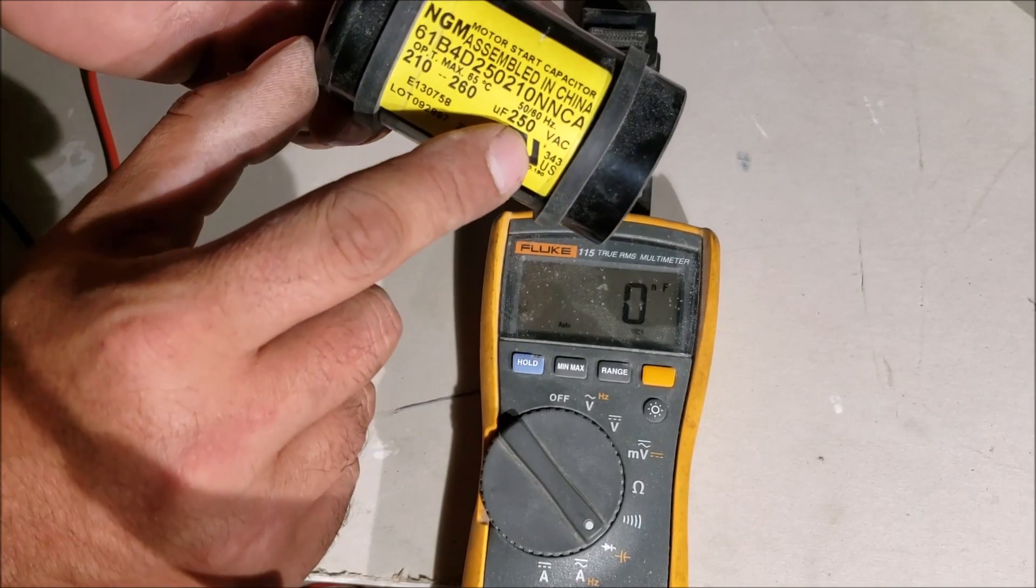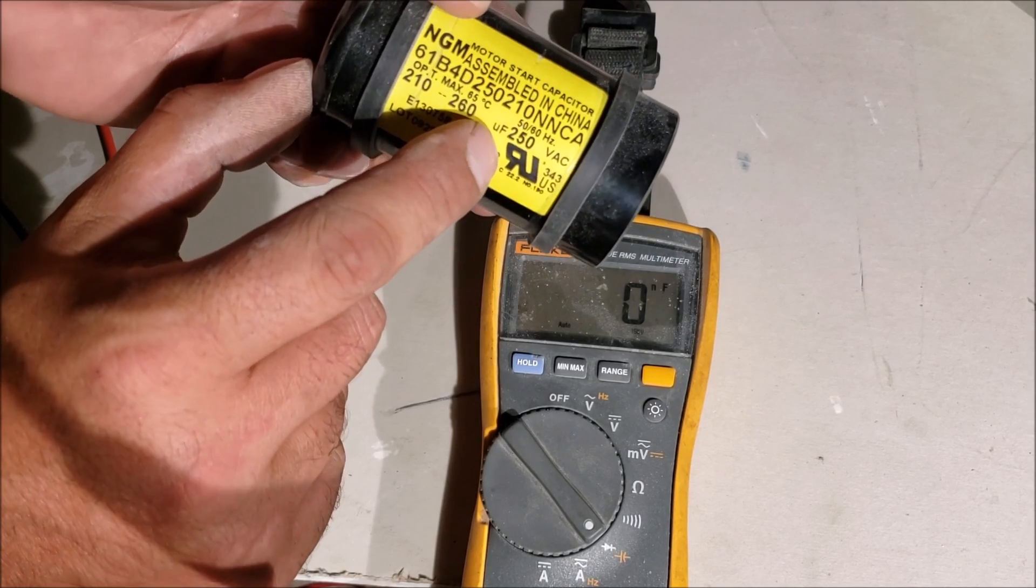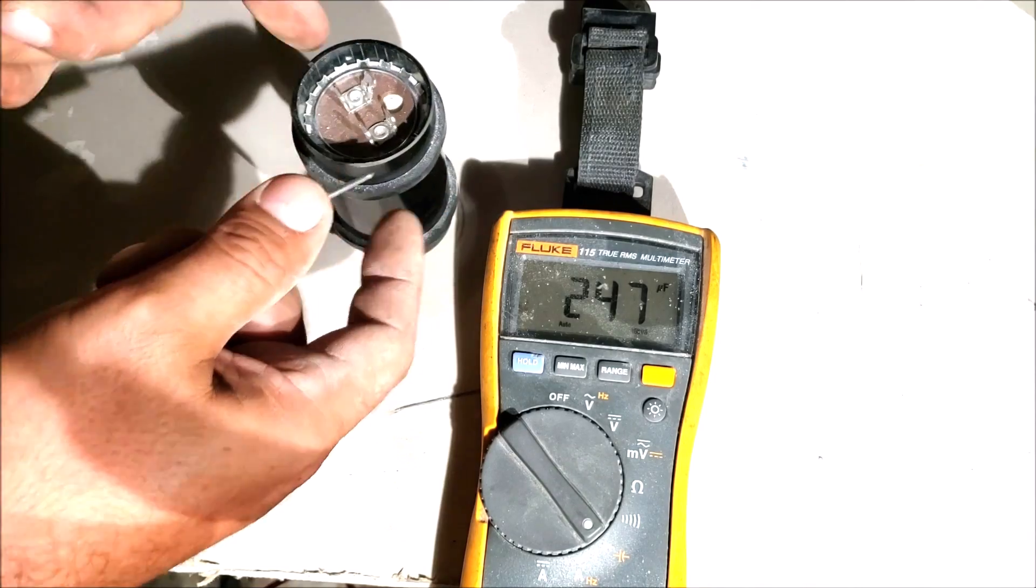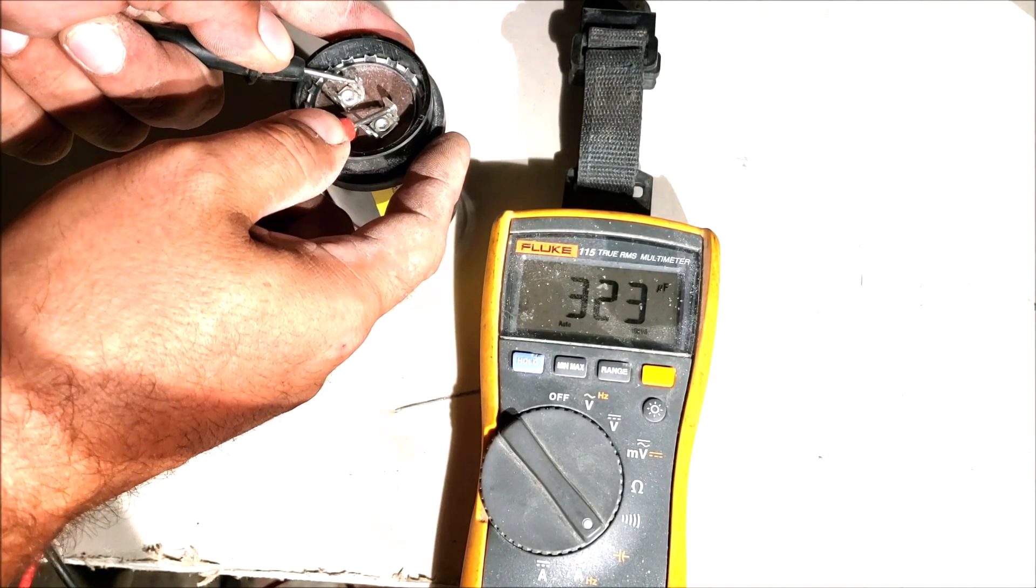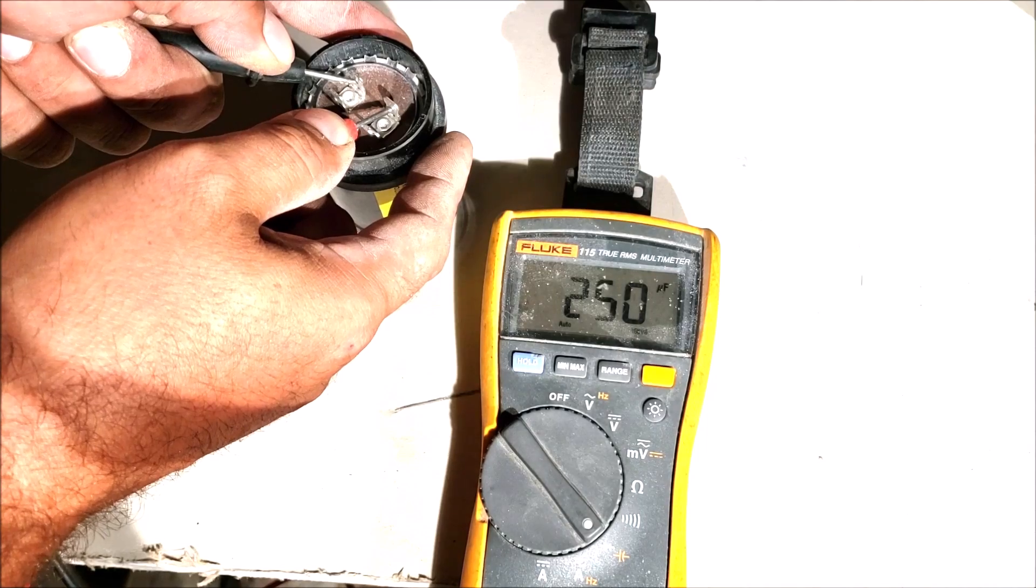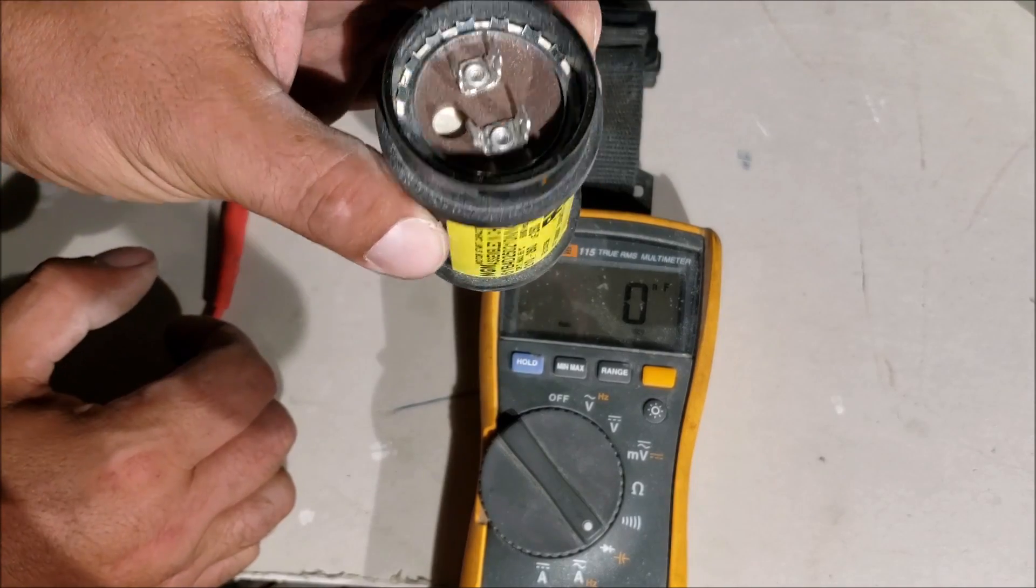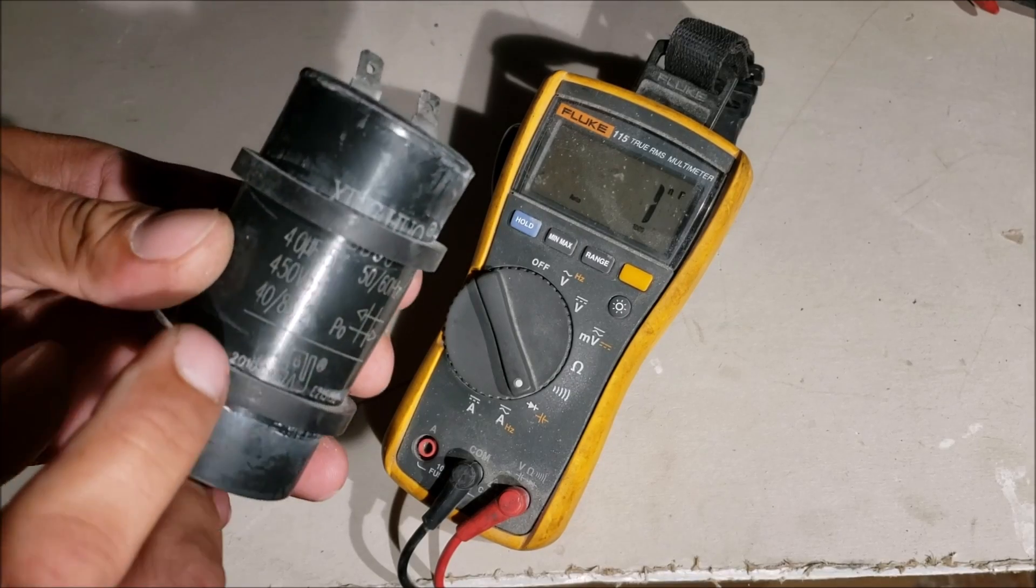This is a start capacitor on an air compressor, 210 to 260 uf, that's the microfarads. We're getting 247. Remember, flip it around, play with it. 247, we're good. This is a good capacitor.